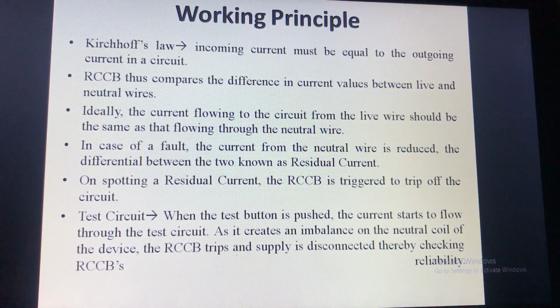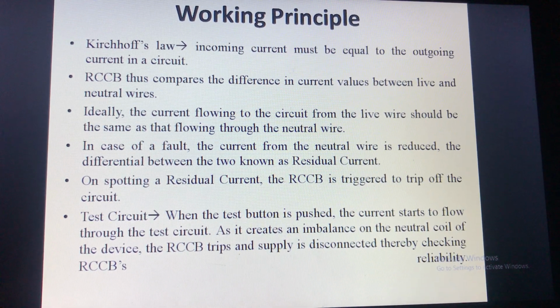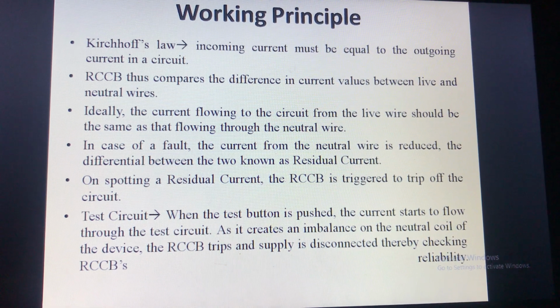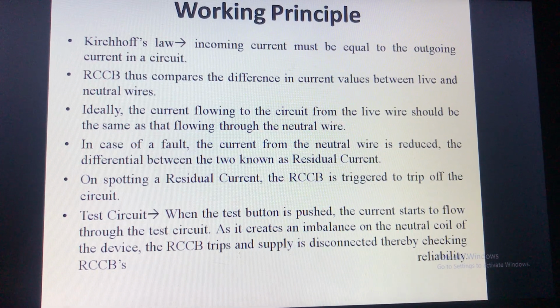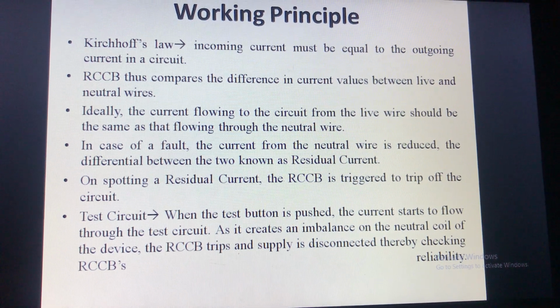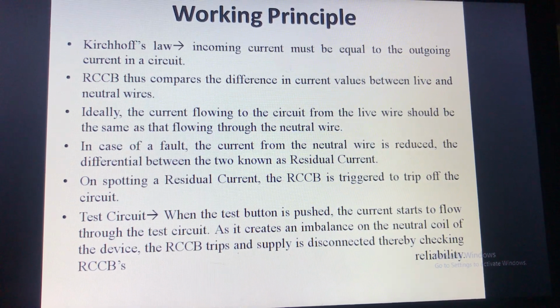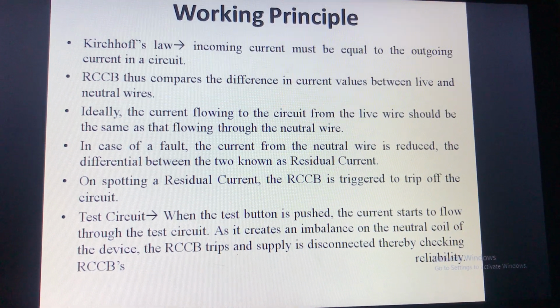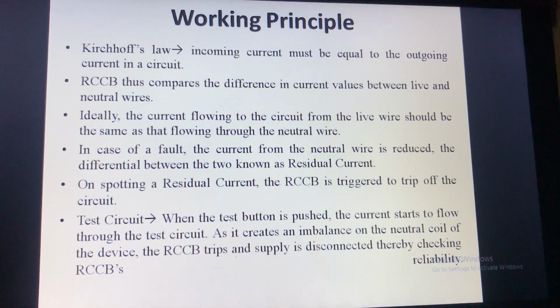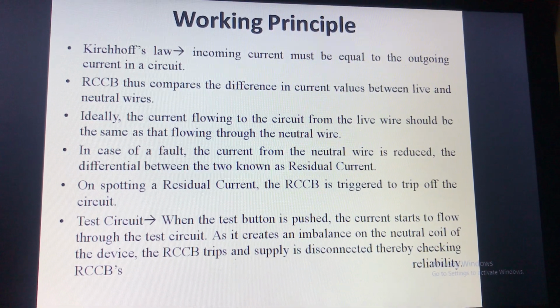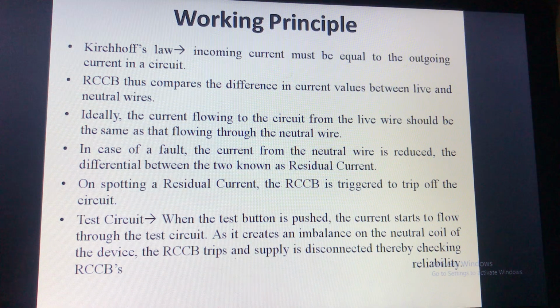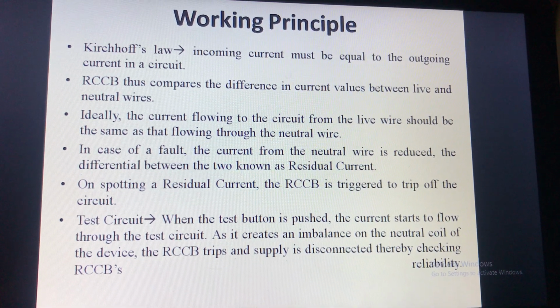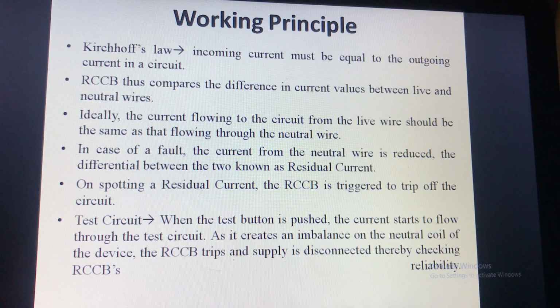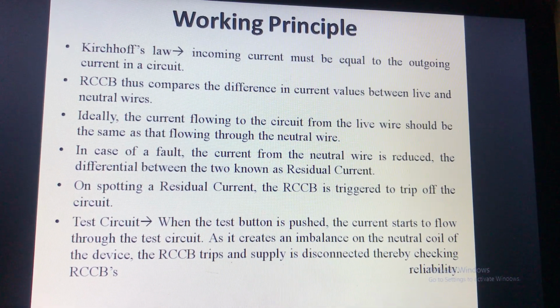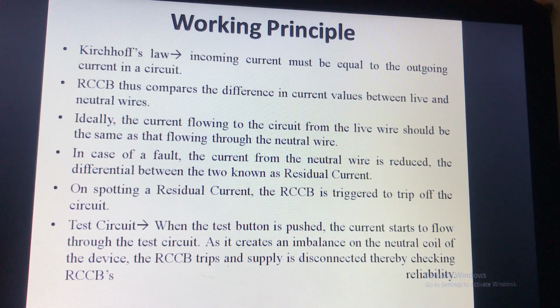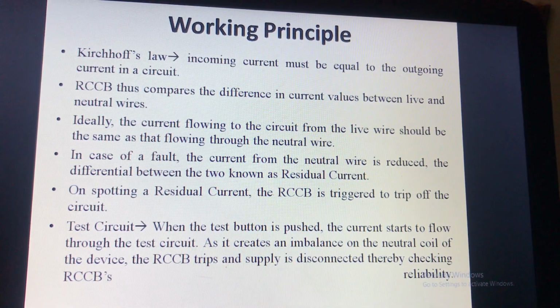So what's the principle behind RCCB? Basically, it works on the principle of Kirchhoff's law, which states that the incoming current must be equal to the outgoing current. So this very principle we are using in RCCB. It will compare any difference in current values between live and neutral wire. Ideally, this current should be the same in case of normal conditions. But in case of any fault, the current from the neutral wire will be different from the current flowing in the phase wire, which is known as residual current. So this residual current is detected by RCCB and the circuit will get triggered.